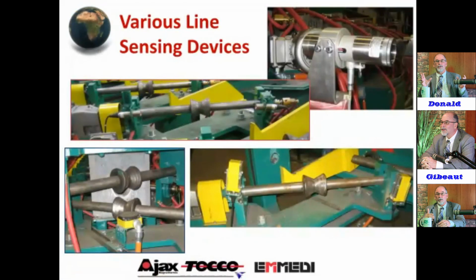Various drives, we looked through the line at the different photo eyes, the infrared units we talked about that control the temperature, and we can actually feed forward with a PID loop and control the power of a second unit in a multi-unit line for a variation in incoming metallurgy and/or ambient temperature.